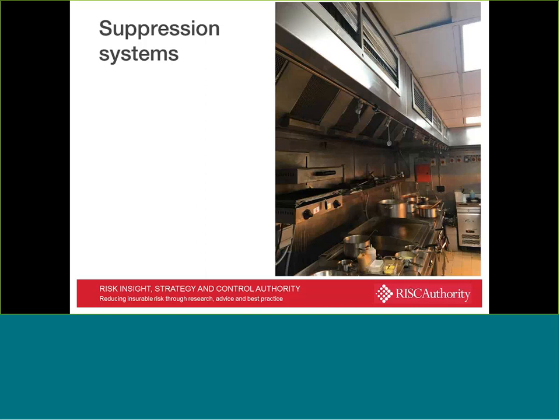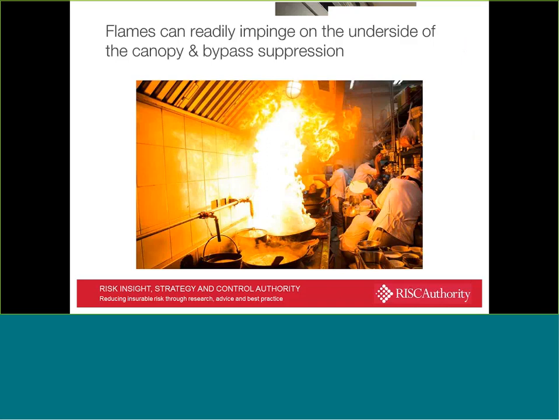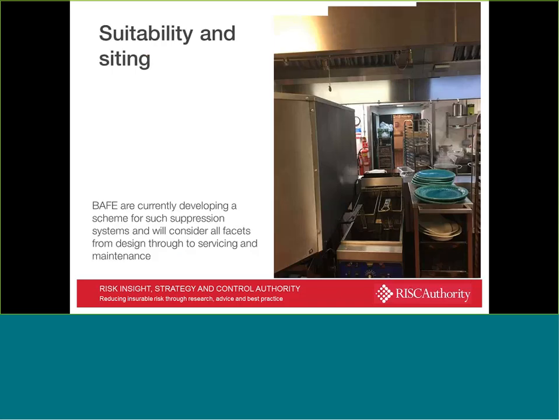Before wrapping up, and I know I've spoken for far too long, so apologies, suppression systems are clearly an important factor in ensuring and maybe minimising the potential for fire to spread up into the ductwork. But I think as we discussed earlier and was shown from some of the photographs, it's not uncommon for fire to be able to spread and bypass whatever triggering mechanism there is for the suppression system directly into the filters, the extract, and up into the ductwork itself if cleaning hasn't been effective.